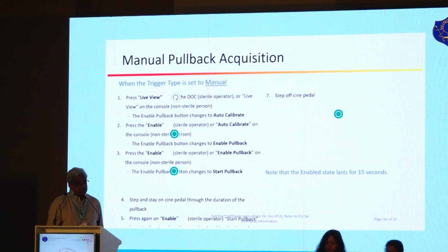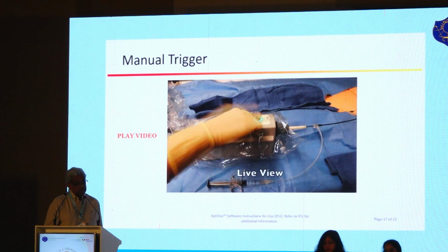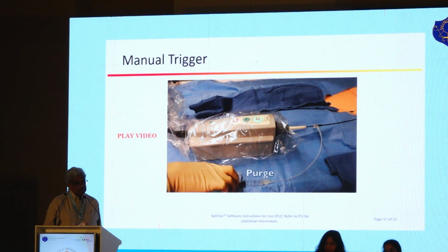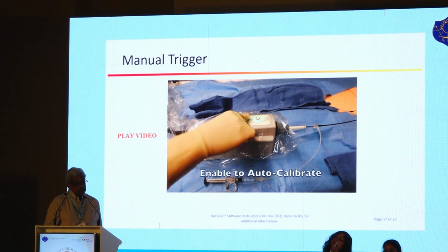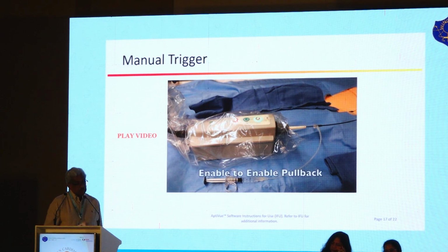When the trigger is set to manual, press live view for the DOC, sterile or live, and step off the cine pedal, view on the console and auto-calibrate. So I think these are the steps that you need to do for the manual. And in the interest of time, I'll just show you quickly what it does. This is how you purge it. Then after you press your enable, you press it again, and then you start your pullback, and by that time you're already on cine and your dye injects.